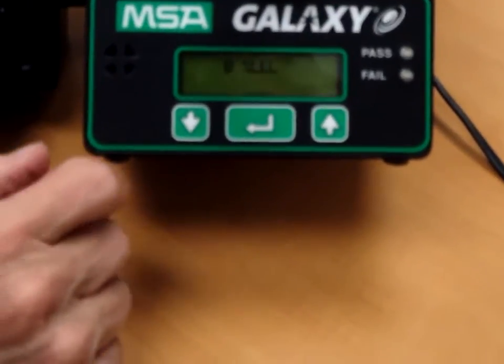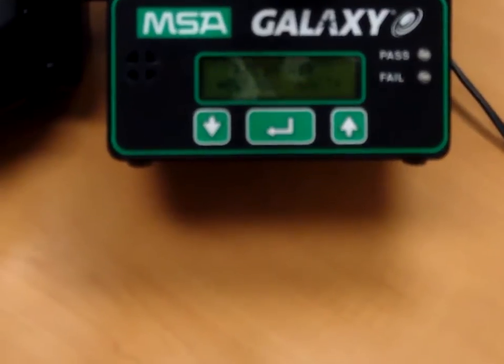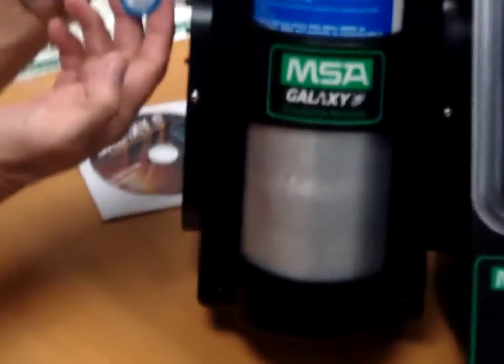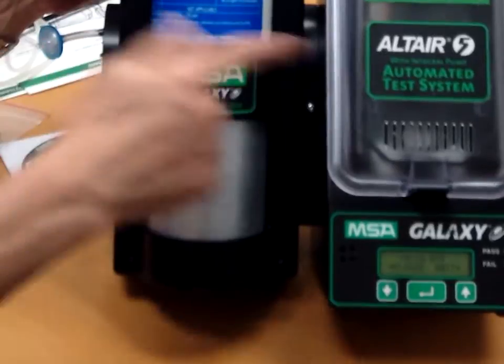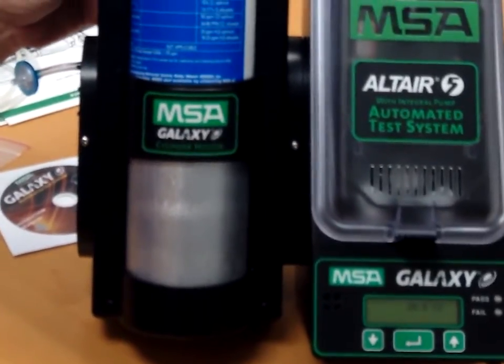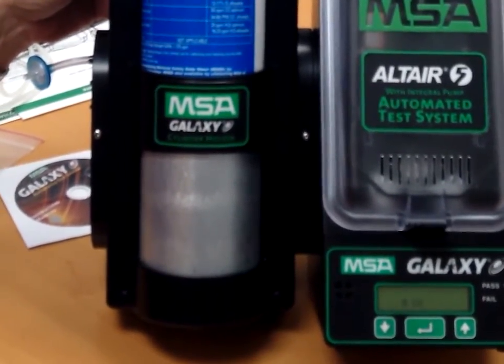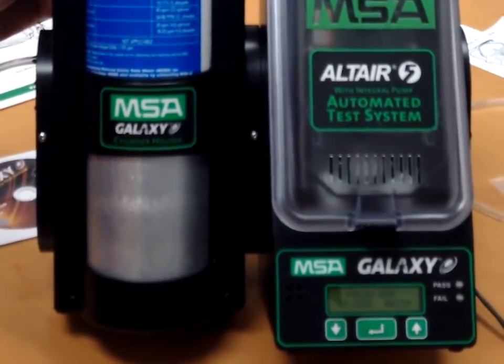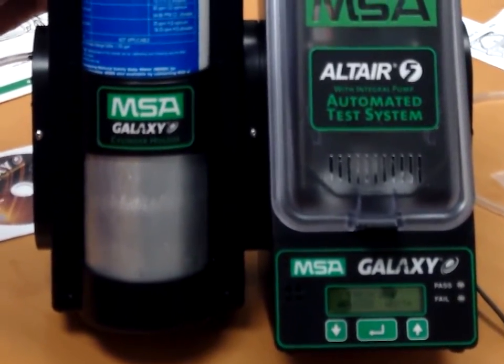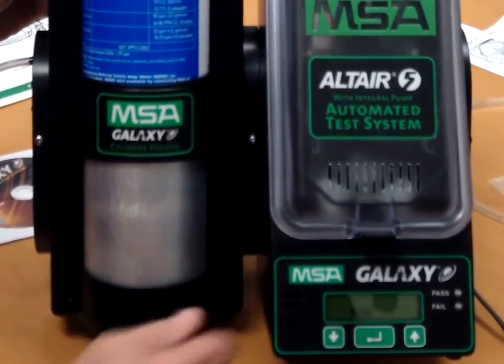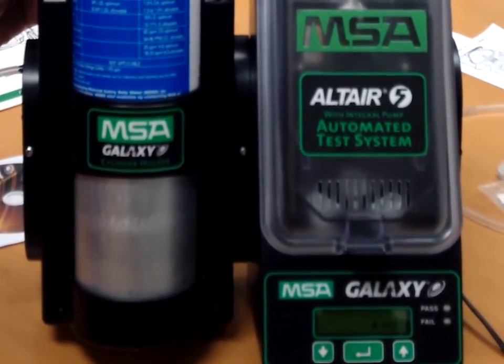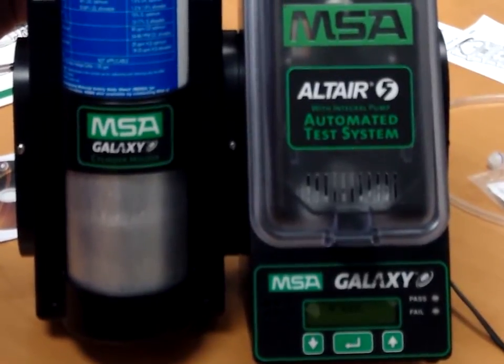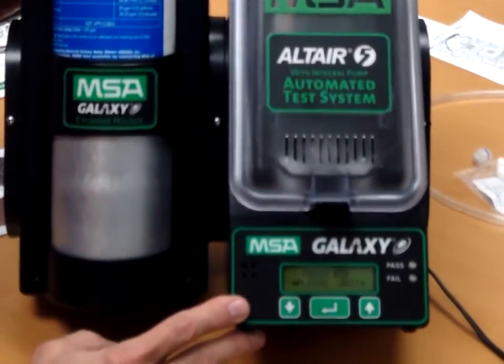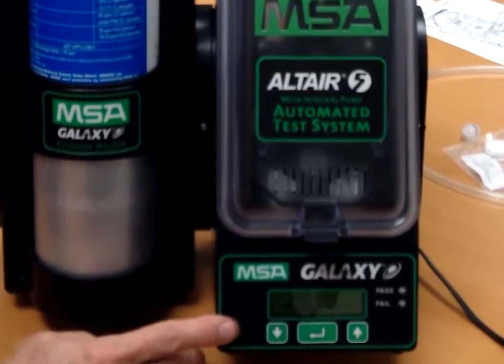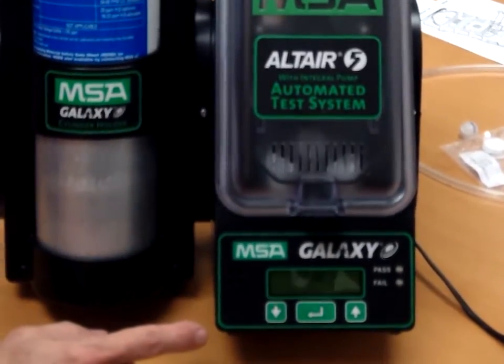And now what is happening, there's the serial number of that unit that you have in there, and it's going to go through and do a fresh air setup. At this point, what it's doing is taking the air from the inlet port over here and running a baseline of fresh air across the sensors. So what we're telling the sensors right now is that we have 20.8% oxygen, 0 on LEL, 0 on H2S, and 0 on the CO. We're going to run through that, which sort of purges out and cleans out the sensor cavity, to make sure that there's no leftover gases, and this will go for about 30 seconds, and at that point it will go into a calibration mode.